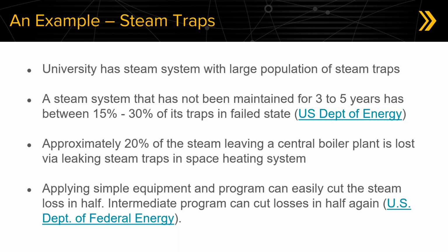I talked about integrating data and getting data into your system in order to take that condition-based maintenance approach. But what if we don't have that information available to us in a data historian or SCADA system that we can integrate? It's not that if we don't have the data we must do some sort of time-based maintenance - we can actually use mobility to trigger inspections to go out and capture information that'll help lead to a condition-based approach. So this is a good example here.